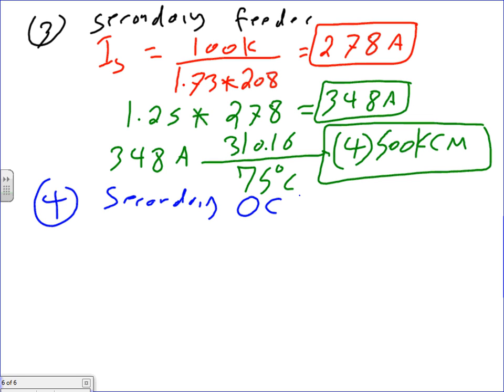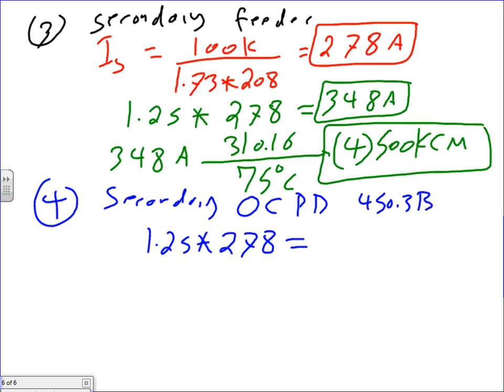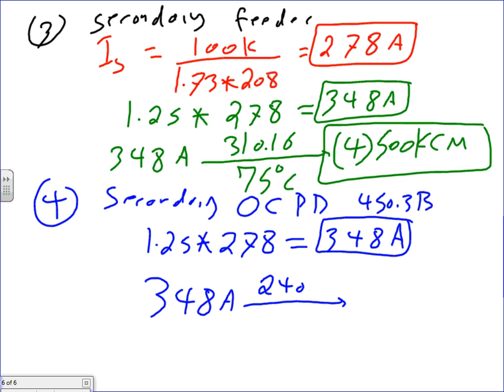Secondary overcurrent protection device. Okay, if you go to Table 450.3(B), on the secondary side, is it 1.25, Holly? Yes. It's 1.25 multiplied by what current? Not the 348, but the 278, the actual secondary current. So for the secondary fuse or circuit breaker, that will get you 348 amps. Then you take the 348 amps to 240.6, and if it's not a standard size, you go up or down.